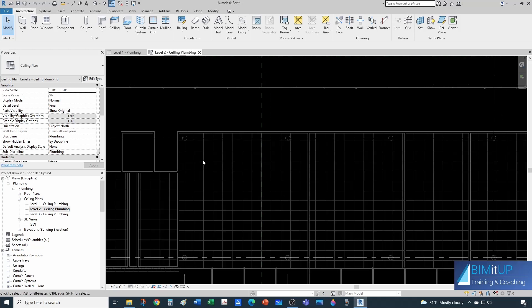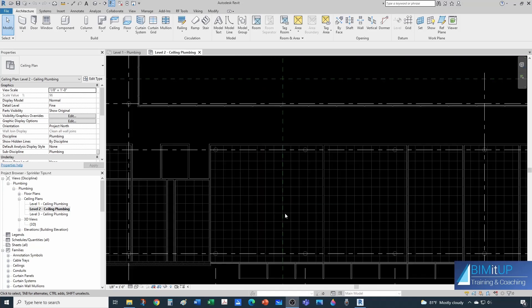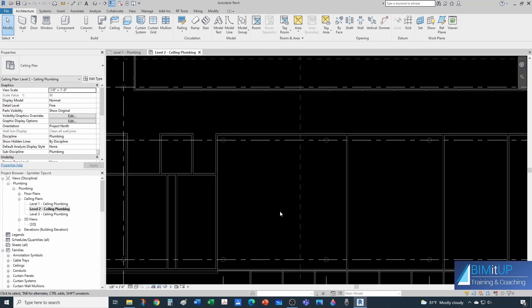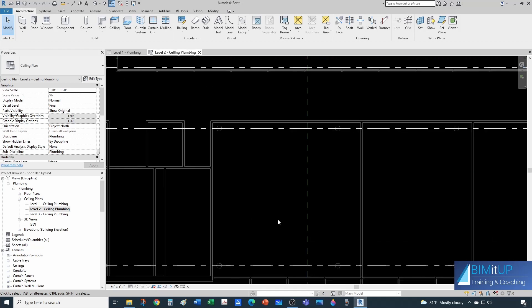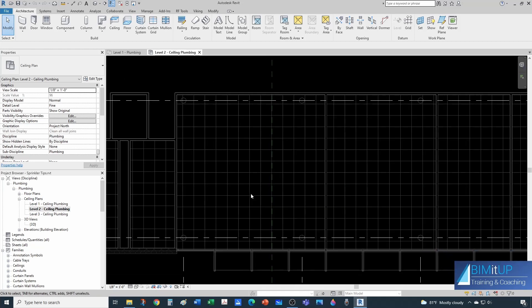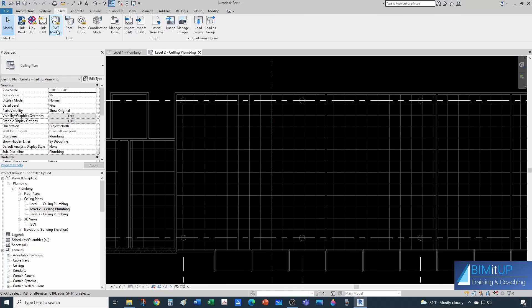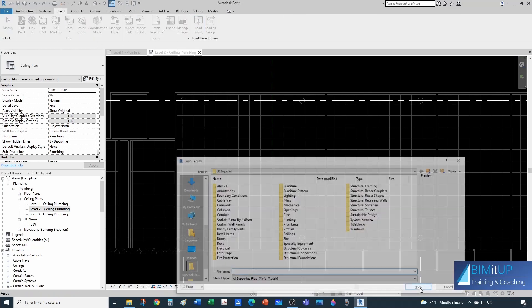I'm going to create a video in the future on how to space sprinklers per NFPA 13 requirements, but for now let's just drop four sprinklers here. Out of the box Revit has some sprinklers but I don't like them too much, so I would recommend you go to the internet and go to either Tyco, Viking, Victaulic, or Reliable or any other manufacturer that you like and download their sprinklers. In this case I'm going to use a Viking sprinkler. I'm going to go to Insert and then I'm going to go to Load Family.